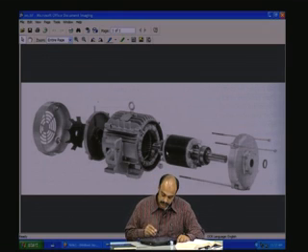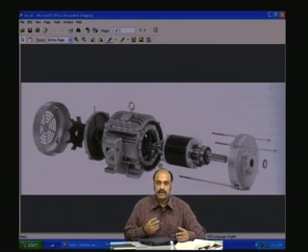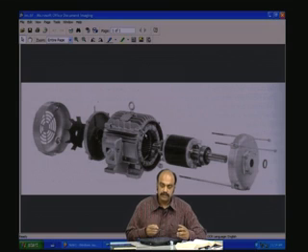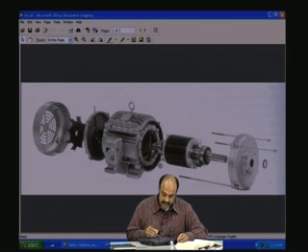So this is the rotor, and then inside here you see some coils or windings, and that is the stator windings which form the various poles, the A phase poles, the B phase poles, the C phase poles, and so on, which are wound on the circumference of this stationary system, and that is called the stator.